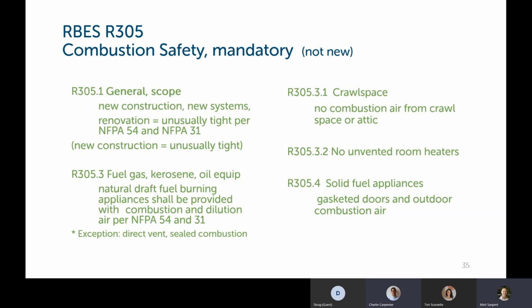For RBES, there is in section 305 mandatory combustion safety requirements, and these are not new. This applies to new construction, new systems, and renovations. And those buildings, those construction types are going to be considered unusually tight per NFPA 54 and NFPA 31. So we're considering renovations as unusually tight as well.